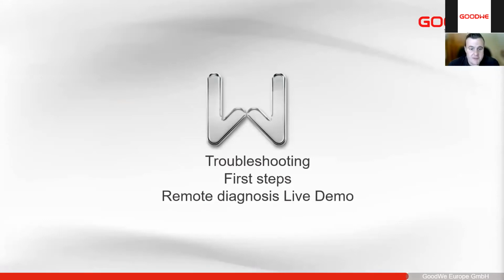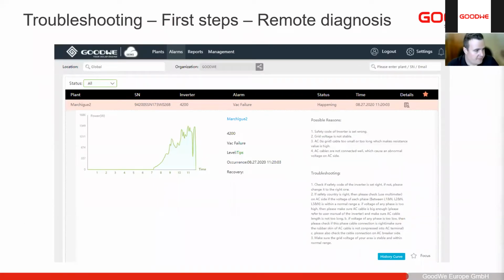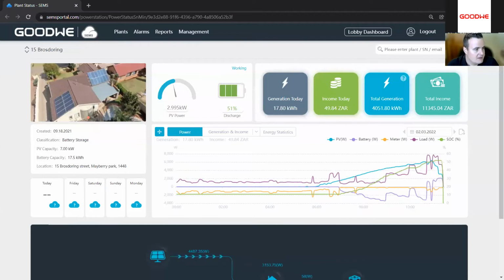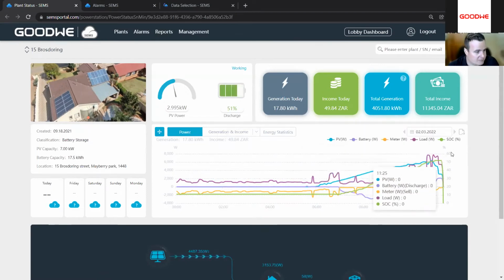So for troubleshooting, these first steps, we're going to do a live demo here. First is going to be the SEMS portal. So when a customer reports there's a problem, one of the first things we can do is come to the SEMS portal. In the SEMS portal, we have a lot of places where we can go to view problems that we're experiencing. I hope you can see my web browser quite nicely now. This is the typical plant on the SEMS portal. As you see, we've got alarms and reports that we can use to look for faults, as well as the general plant overview.